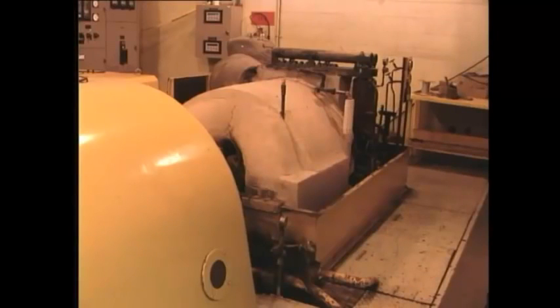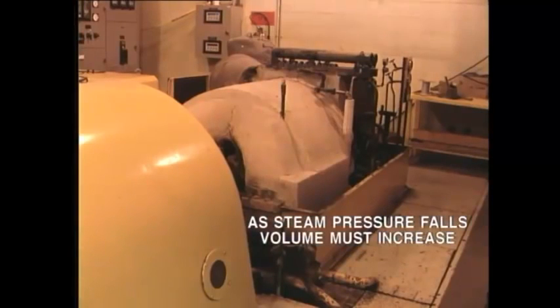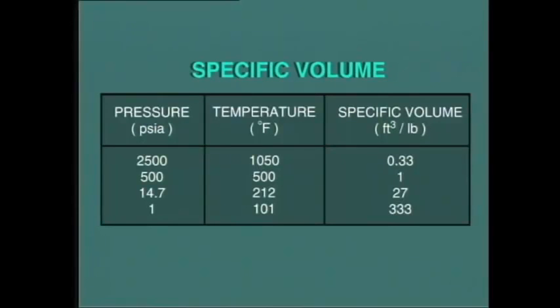This problem of specific volume is of concern to us when we consider the steam passing through the turbine. We know that the steam pressure falls, and consequently its volume must increase as it approaches the low-pressure end. In fact, the change in specific volume of steam is quite dramatic, as we can see in this table. 1 pound of steam at 2,500 psia and 1,050 degrees Fahrenheit occupies a space of 1/3 of a cubic foot. At 500 psia and 500 degrees Fahrenheit, the specific volume is 1 cubic foot. At atmospheric conditions, the volume occupied by 1 pound of steam is 27 cubic feet. And in the case of a condensing turbine, where we have steam exhausting at, say, 1 psia, the specific volume is 333 cubic feet per pound.